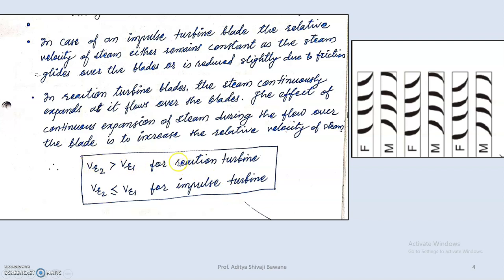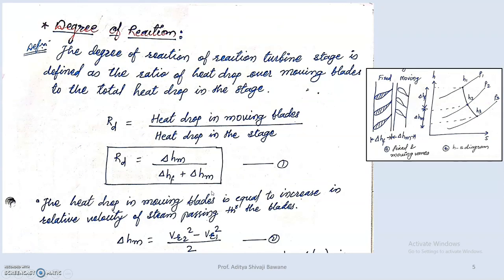The degree of reaction is defined as the ratio of the heat drop over a moving blade to the heat drop over a complete stage. One fixed blade and one moving blade together constitute a stage. So Rd (degree of reaction) equals ΔHm divided by the total heat drop across the stage, which equals heat drop across the fixed blade plus heat drop across the moving blade: Rd = ΔHm / (ΔHf + ΔHm).